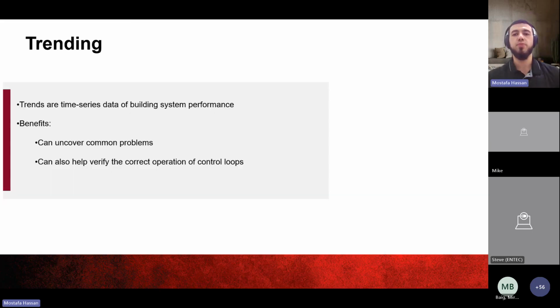So trending. Right. A trend in a building automation system is a data point sampled over time or based on a change of state, or change of temperature. So in 15-minute intervals, 5-minute intervals, right? When you're trending that specific temperature, humidity, whatever you need, right? So a couple of benefits of trend analysis, right?